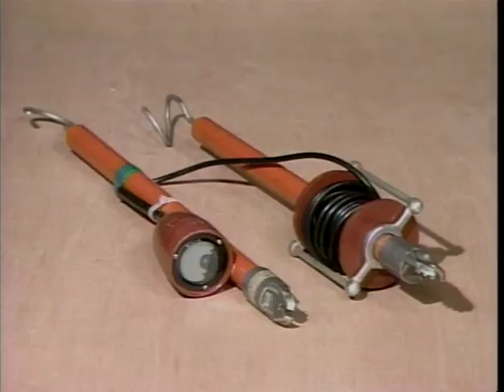Every tester has a safe operating range, requires routine inspections, and must be used properly to get accurate test results. For example, this phasing test set has a safe operating range from 0 to 16,000 volts. If you used this tester on an energized circuit that exceeded this range, you could damage the tester, or worse, get a false indication of the absence of voltage on a circuit. Now, in this situation, assuming the circuit is dead could place you in danger when you work on the circuit.